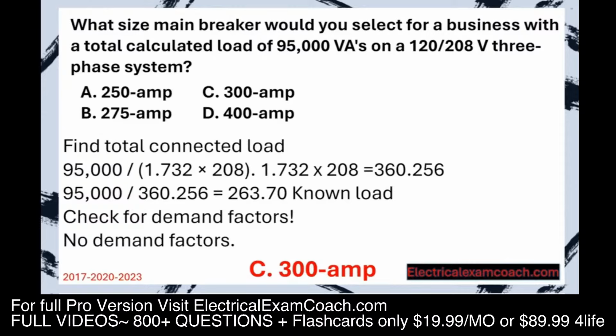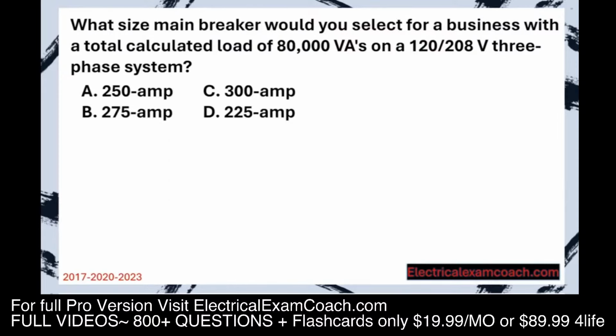Let's get to it. What size main breaker would you select for a business with a total calculated load of 80,000 VAs on a 120/208 three-phase system?